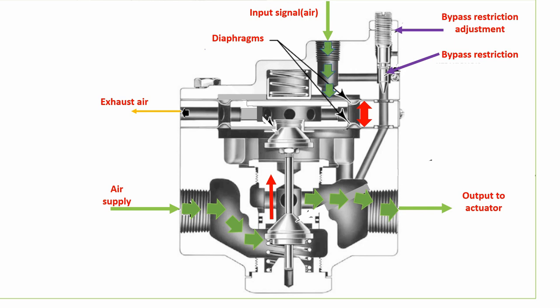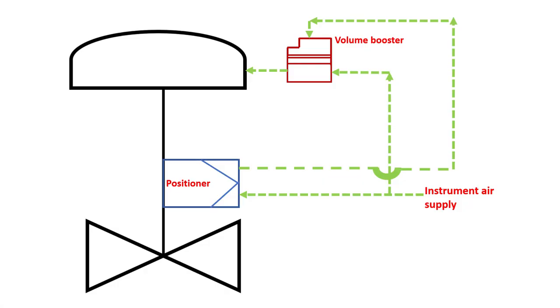There are two diaphragms inside the volume booster, and air balances between the two diaphragms. On the bottom side, instrument air supply comes in from the instrument air header. There will be forces applied between these two diaphragms. Once the input air signal enters the volume booster, there will be an imbalance in the diaphragm, which causes the plug to move upward. This lets the instrument air supply flow from the volume booster input to the output, which goes into the actuator. The volume booster takes the positioner output as an input signal and amplifies it into a direct air flow from instrument air supply to the actuator.